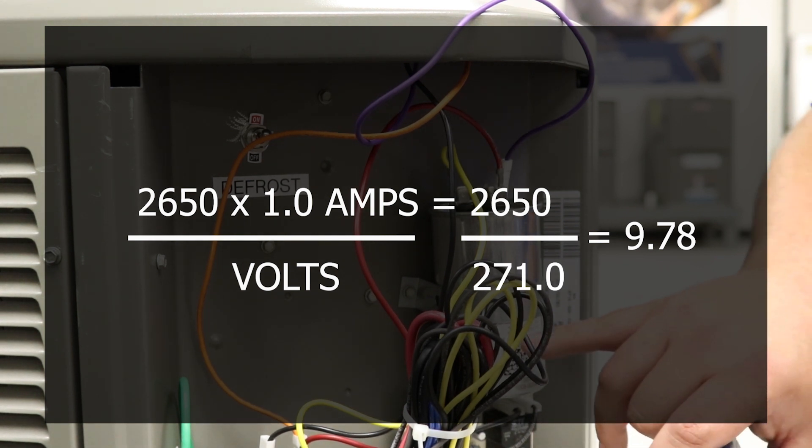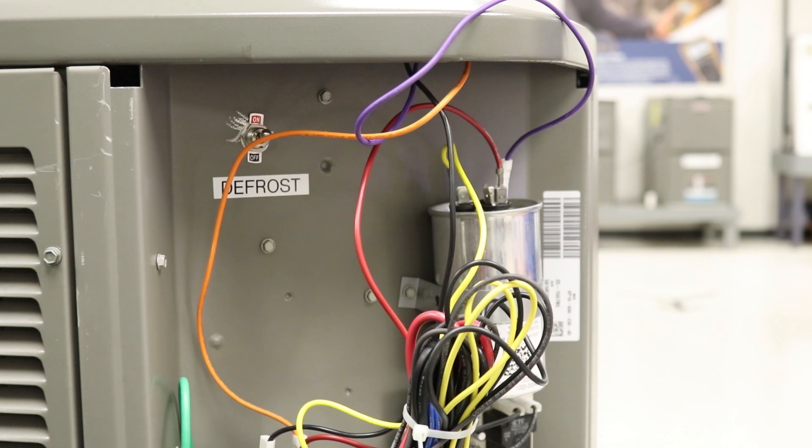With this particular capacitor, it is a 40 plus 10. So we are at 9.7 while that fan is operating. So on the fan side, that 10 side, we know that we're good.